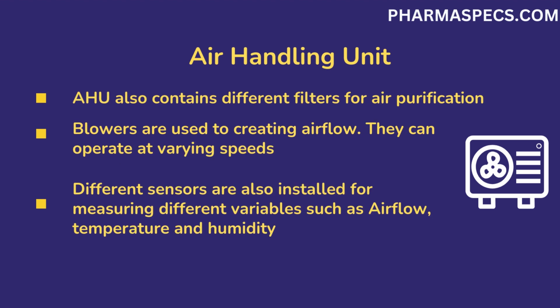Air handling unit also contains filters for purification purposes. These filters remove particles from the air as it passes through AHU. Type of filter depends upon the area requirement and the process being carried out. Blowers are used to generate airflow, which passes through various sections of AHU. The blower can operate at varying speeds depending upon the area requirements. Instrumentation and sensors are also used in AHU to monitor various parameters of air as it passes through different stages.